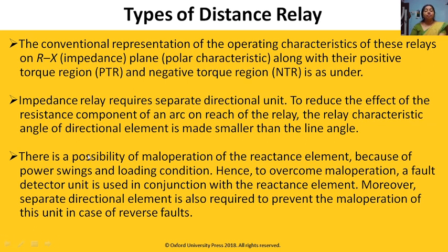To reduce the effect of the resistance component of an arc on the reach of the relay characteristic, the angle of the directional element is made smaller than the line angle. There is a possibility of mal-operation of the reactance element because of power swing or loading conditions. Hence, to overcome the mal-operation, a fault detector unit is used in conjunction with the reactance element. Moreover, a separate directional element is also required to prevent mal-operation of this unit in case of a reverse fault. So we require a directional unit.